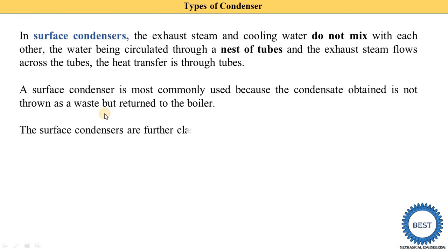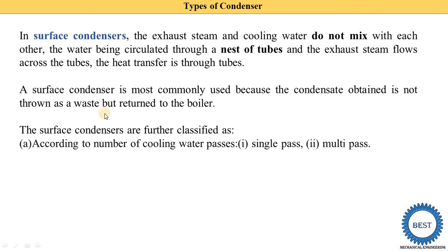Surface condensers are further classified. First, according to the number of cooling water passes — meaning how many times the cooling water is passed inside the condenser. A single pass means the cooling water enters from one side and exits from the other. Sometimes the cooling water is passed two, three, or four times, which is called multi-pass.